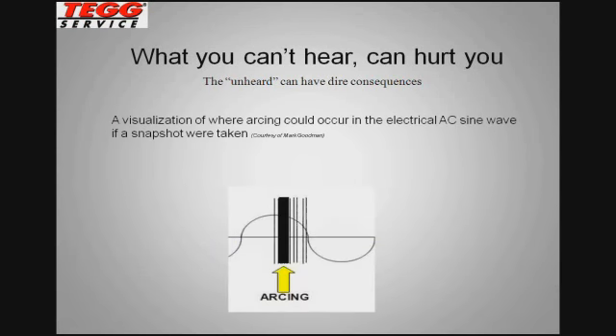If you want to associate this with an electrical sine wave, I was over in Australia a couple years ago with Mark Goodman from UE Systems, and he put this together relative to the electrical sine wave, which I thought was a really good way of describing where these discharges are occurring on that cycle. And if you look, there's not a real distinct pattern with respect to time when those discharges occur. With arcing, it could be anywhere on the sine wave, which is why there's no pattern in either the frequency domain or the time domain. So you could have a discharge anywhere on there. It could be visualized in a very similar fashion as we saw on the previous slide.